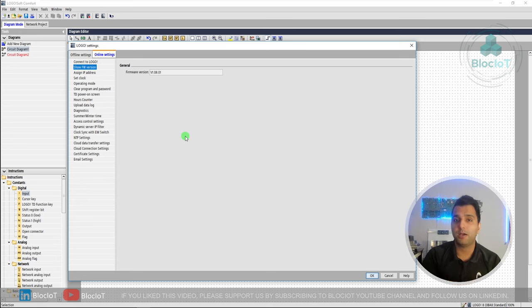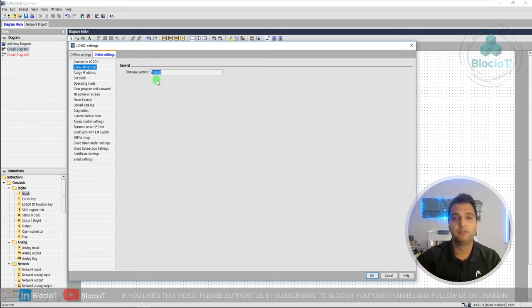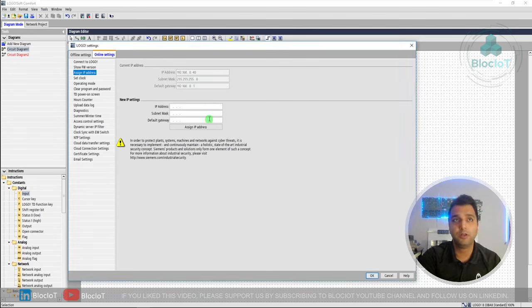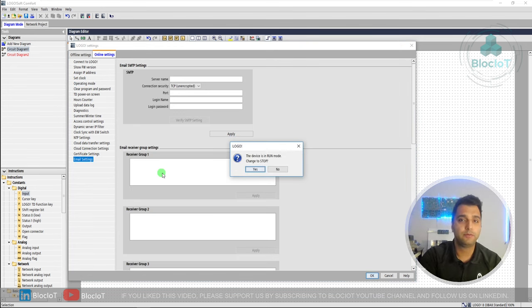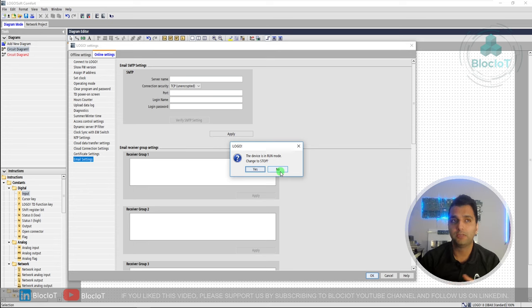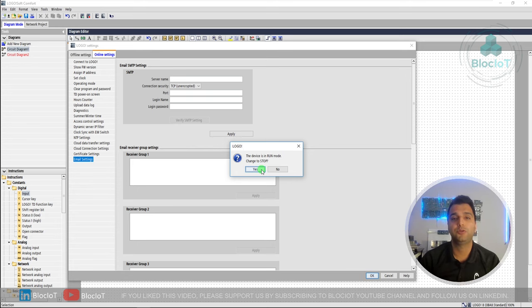Once connected, you are interacting with your Logo in real time, so be careful what you change. From here you can see your firmware version, assign the IP address, set the clock, change the operating mode — Logo can be master or slave — and set up advanced features. Note that for changing some settings, the Logo must be in Stop mode. If you are working on a Logo in a production environment and you hit Stop, the Logo will not execute your logic, which can cause damage, so be very careful.